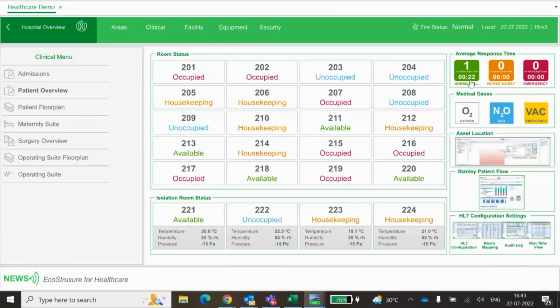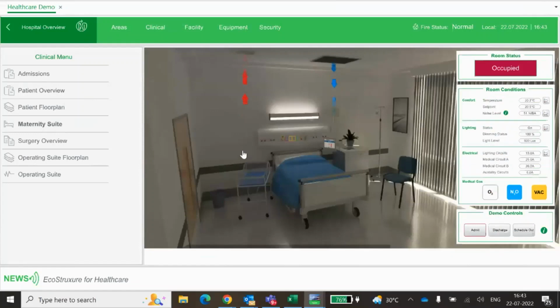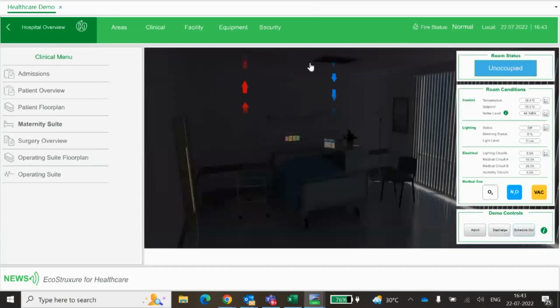So this integrated approach with various systems and the BMS is effective. If a patient goes out for testing, like a blood test or CT scan, the occupancy sensor will sense that he has not checked out but has left the room, so it goes into unoccupied mode. The lights automatically go off, the blinds close, ensuring energy efficiency. The air conditioning cannot be switched off since the patient hasn't checked out, so it runs at a higher set point to optimize energy.